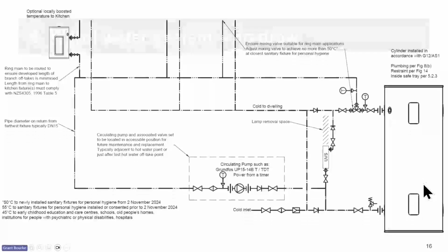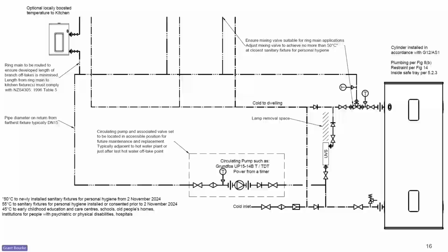So let's have a look at that warm water system. In the middle of the night, in the middle of the day, nobody's home, and there's no draw on the system. So what we've got is a fixed volume of water chugging around the ring main. As it goes around the ring main, it's going to lose some heat. So you see I've changed the colours from orange to yellow to indicate that it's lost a bit of heat.